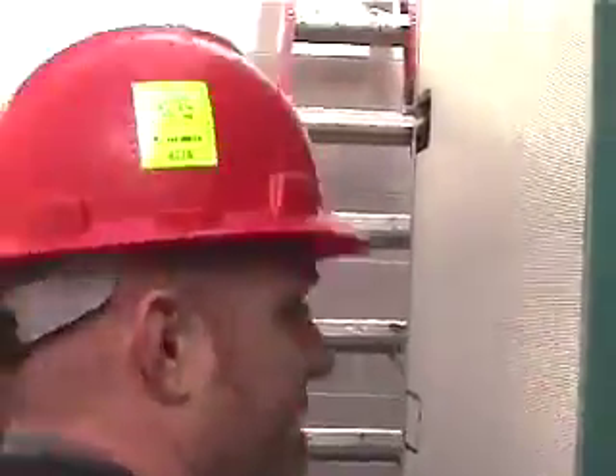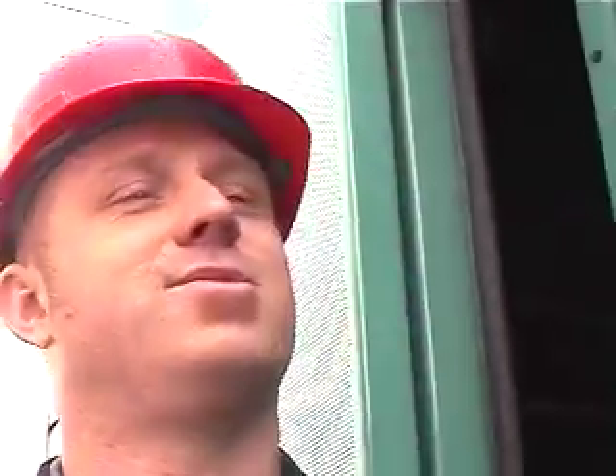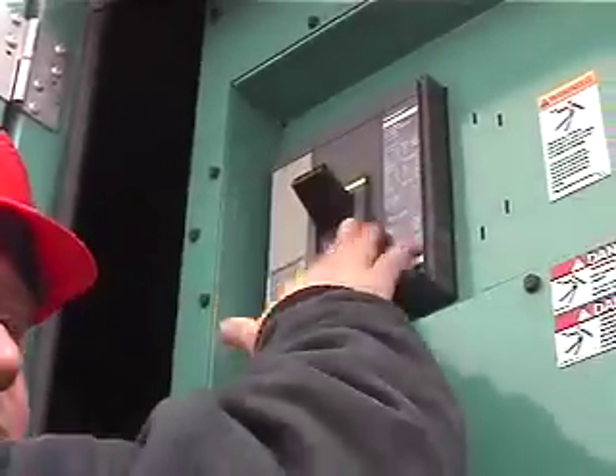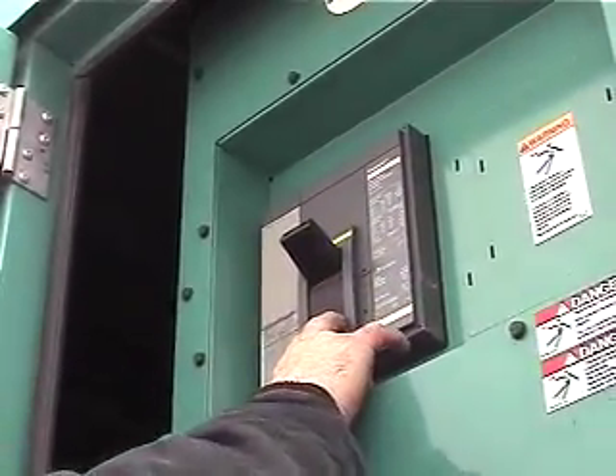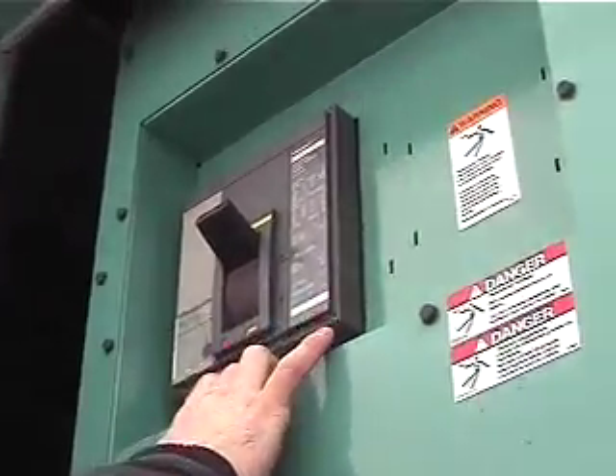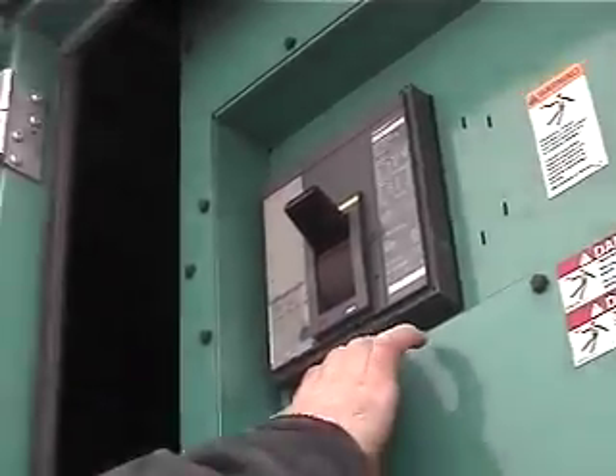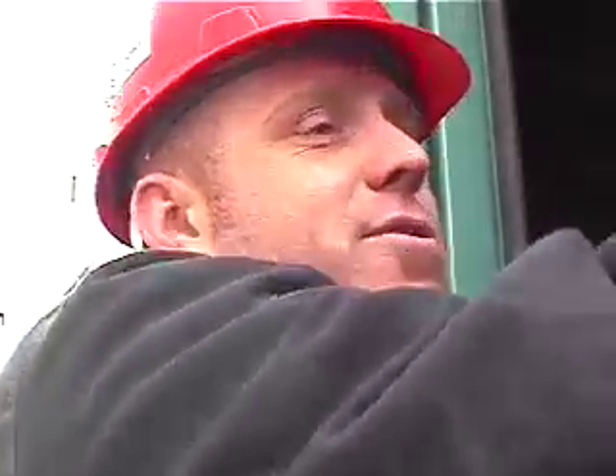Okay, I'll hit a real quick scenario with you. Power goes out, generator starts, neither one of your transfer switches transfer. We have that happen. So the very first thing that I check is this breaker right here. This is the output breaker from the generator. If this is turned off, nothing can happen inside. So that's the first thing I'm going to check.